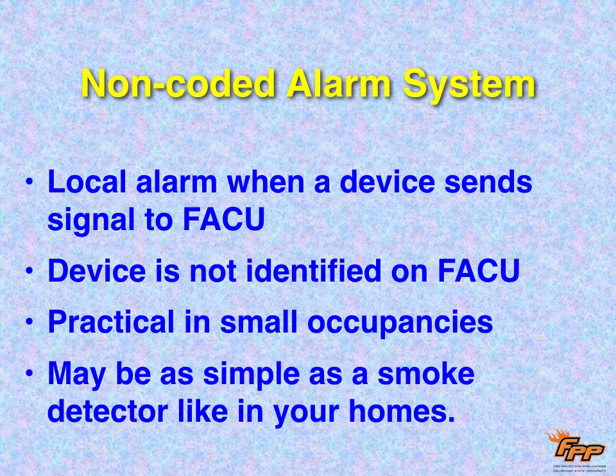So in the old days, they had these non-coded alarm systems. Now, we still have them a little bit when we just have a local alarm. When a device sends a signal to an FACU, it puts out a signal, a sound, but it doesn't identify where the problem is. And these are small occupancies. It's just going to make a sound or put off strobes to alert people in the building. So these are local alarms. There's no message that goes to the fire department or to a monitoring company. So a non-coded alarm system might be as simple as a smoke detector in your home that's battery operated. It senses the smoke and then it puts out an alarm sound.